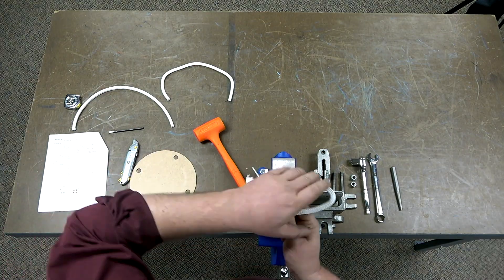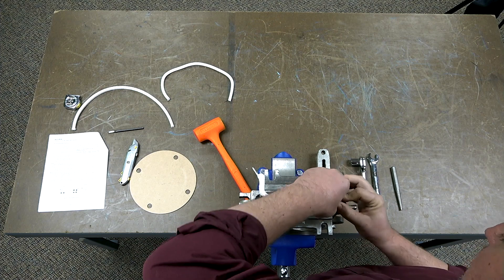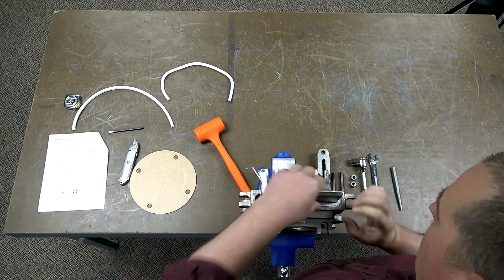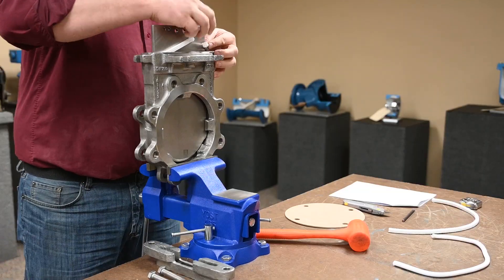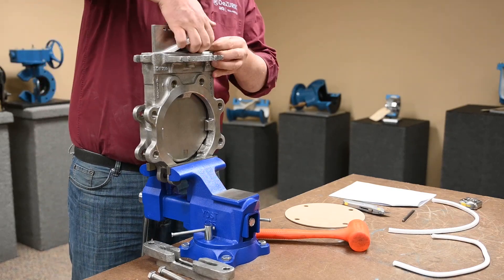Insert the packing into the packing chamber around the gate, starting on the long side of the packing chamber. Make sure the length is accurate and the ends meet with no gap or overlap.